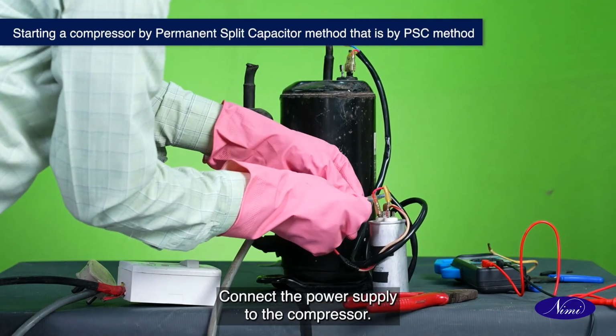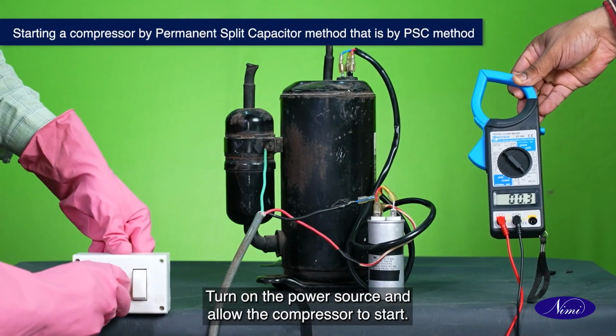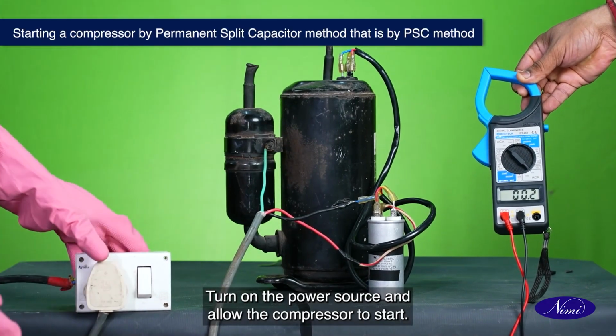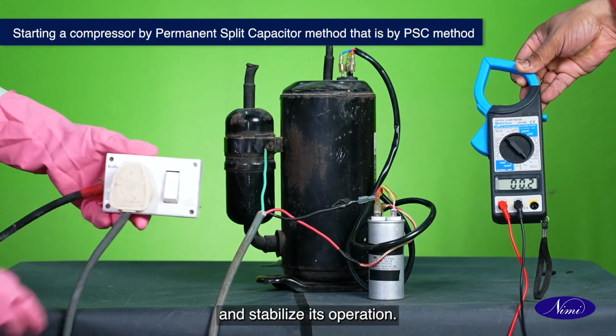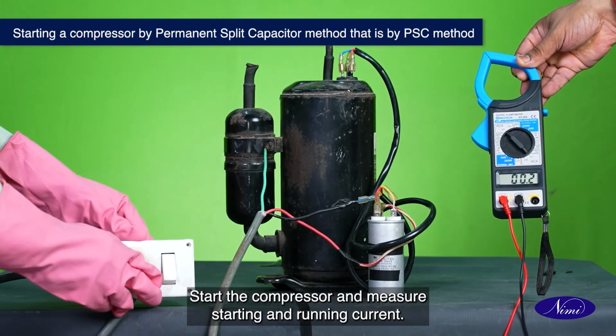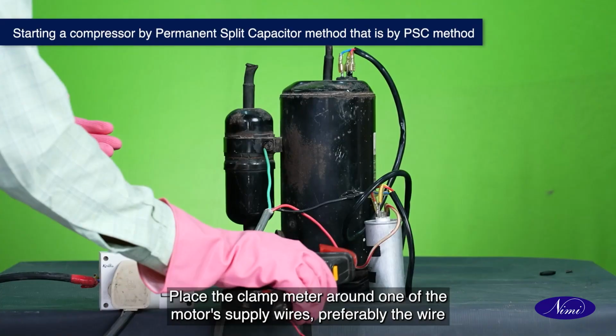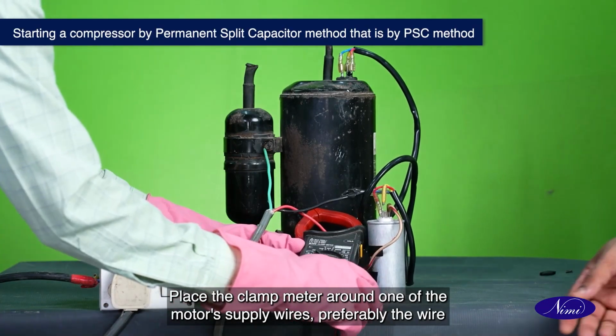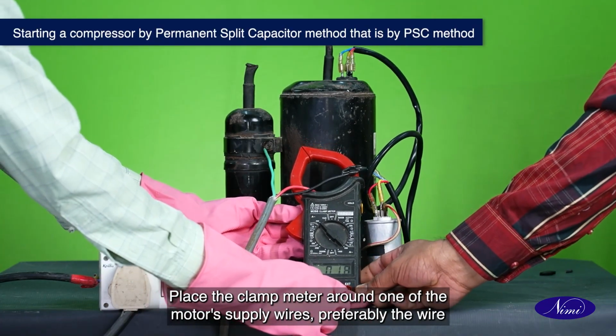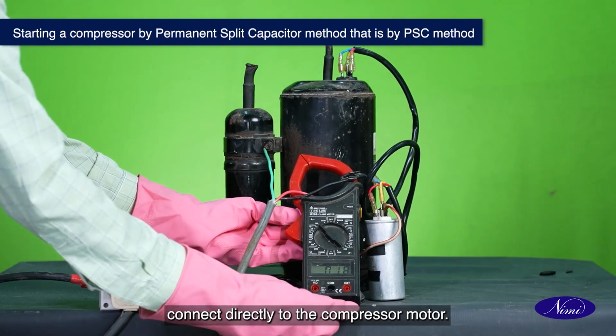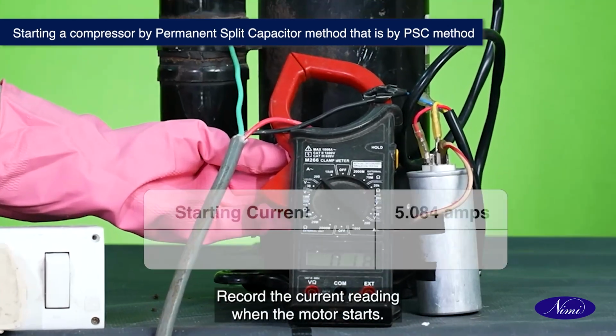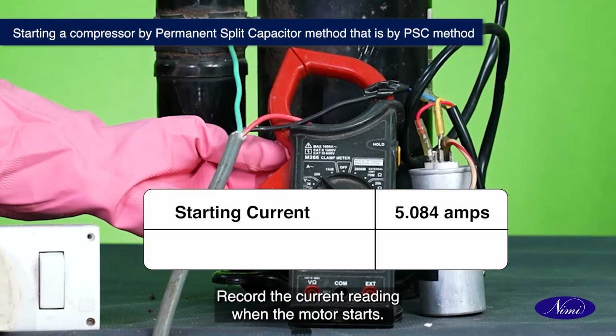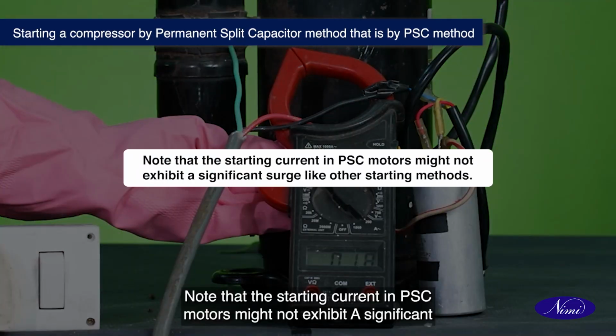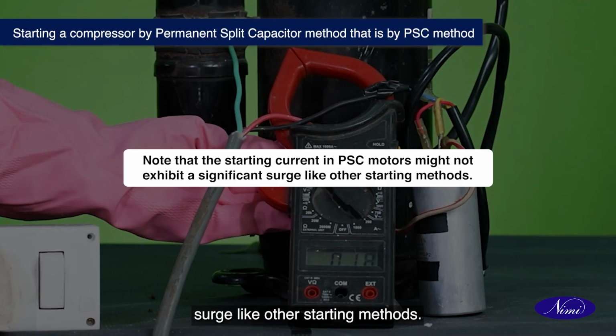Connect the power supply to the compressor, turn on the power source and allow the compressor to start and stabilize its operation. Start the compressor and measure starting and running current. Place the clamp meter around one of the motor's supply wires, preferably the wire connected directly to the compressor motor. Record the current reading when the motor starts. Note that the starting current in PSC motors might not exhibit a significant surge like other starting methods.